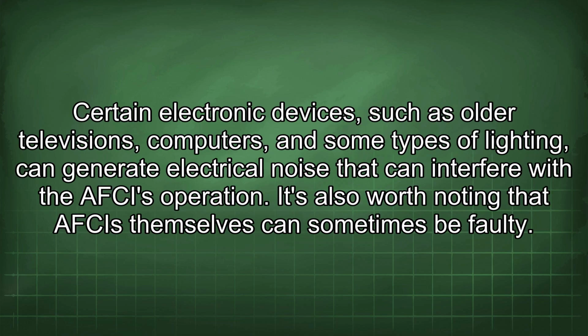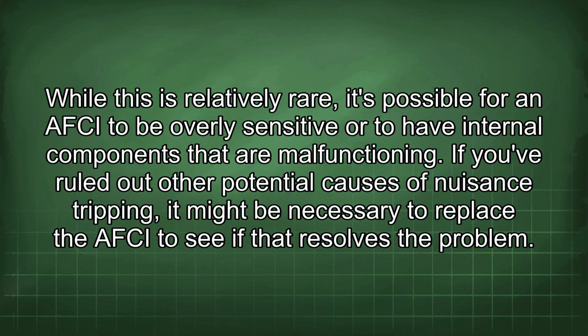Certain electronic devices, such as older televisions, computers, and some types of lighting, can generate electrical noise that can interfere with the AFCI's operation. It's also worth noting that AFCIs themselves can sometimes be faulty. While this is relatively rare, it's possible for an AFCI to be overly sensitive or to have internal components that are malfunctioning. If you've ruled out other potential causes of nuisance tripping, it might be necessary to replace the AFCI to see if that resolves the problem.